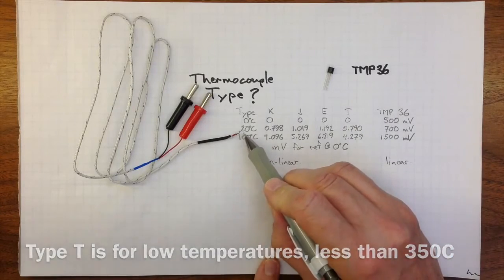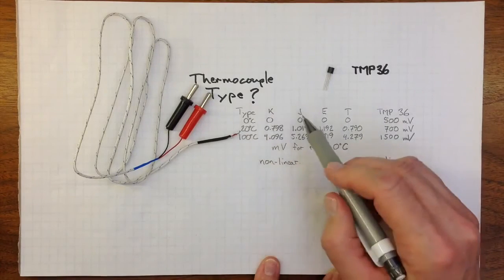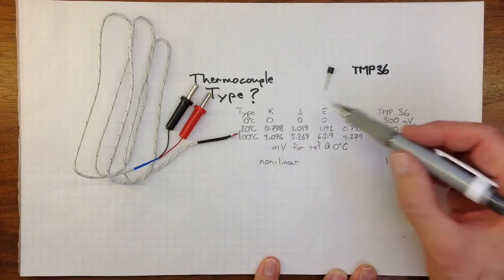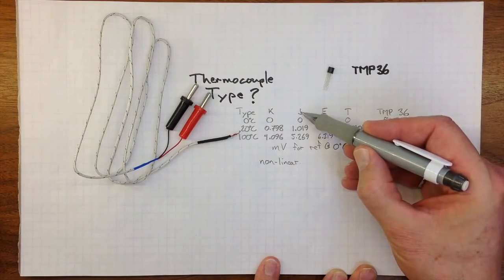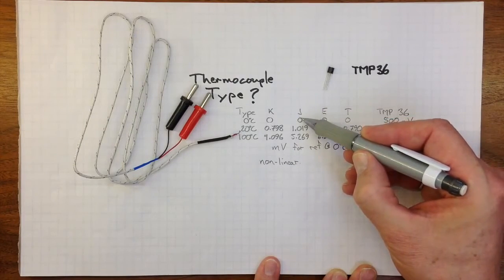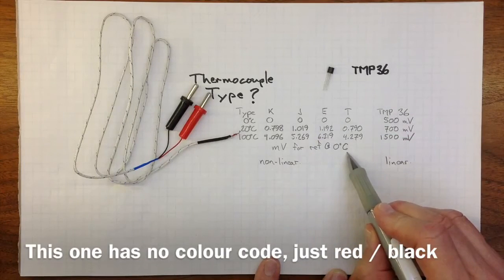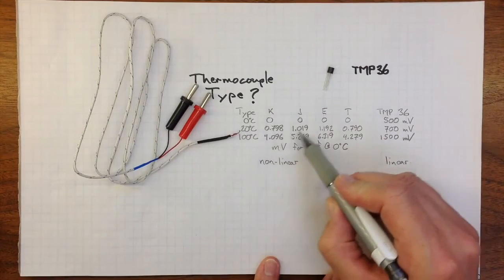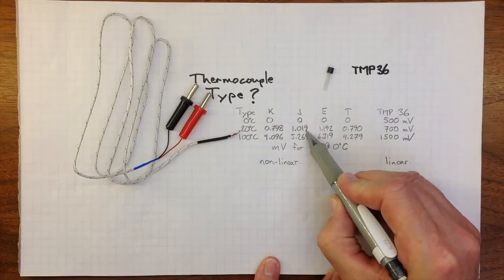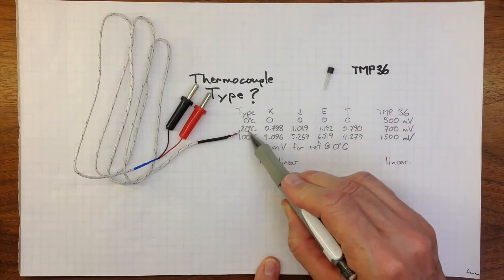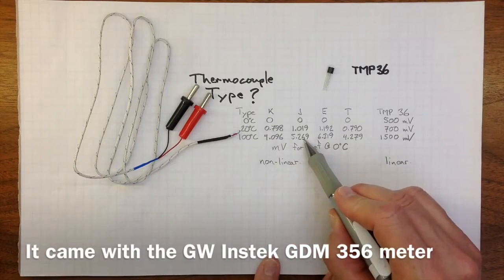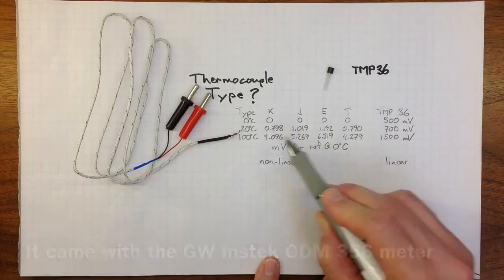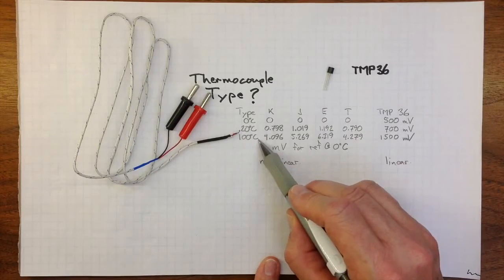Different metals give different potentials from the thermocouple. For example, if this was a type J thermocouple, we'd expect to see with the reference junction at zero degrees Celsius, no voltage if the bead was at zero degrees Celsius, or about a millivolt if the bead was at 20 degrees Celsius, or a little over five millivolts if the bead was at 100 degrees Celsius.